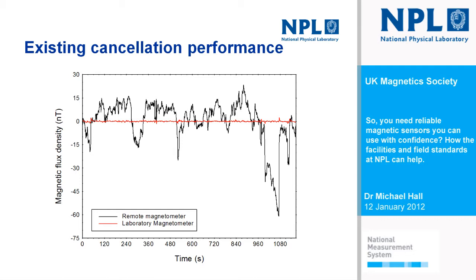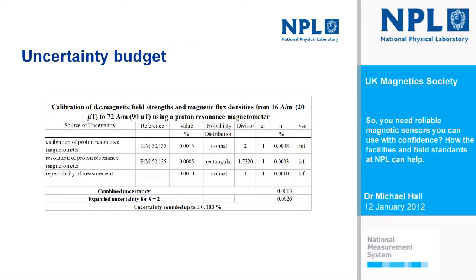So we have to set the system up to be able to live and remove those changes. So what happens if we use that low magnetic field cancelled environment, where we reduce the ambient down to less than 1 nanotesla, to calibrate, to generate magnetic fields? What's the uncertainty that we have? Well, because we've got such a quiet environment and very, very small variation in the ambient magnetic field, the repeatability is excellent, and the contributions to the budget on measuring a magnetic field are actually very small. Here we see a budget with the expanded uncertainty, so that's a 95% k equals 2 uncertainty, rounded up to 0.003%. That's on the measurement of the magnetic field.